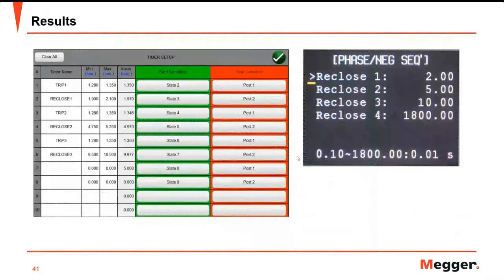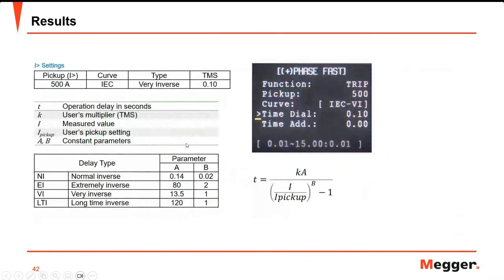Now we will go to the results. We can compare the settings to the measured values that we get from the SMRT. Comparing the settings and the results — they are very near, only 30 milliseconds difference, which is within the allowable limits for reclose one. For the assessment of the overcurrent results, you can use the time-current formula: substitute the test current in the numerator and the settings in the denominator. Using the curve constants, you can calculate the expected nominal time.